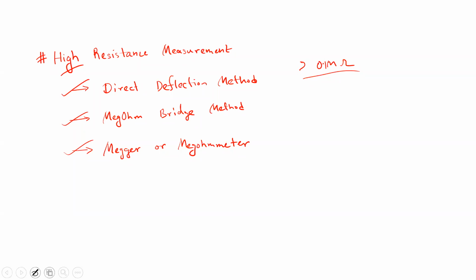First, let us begin with the direct deflection method. Insulation resistances are normally considered to be high resistances. It could be cable insulation provided in a cable or between any electrical conductors.